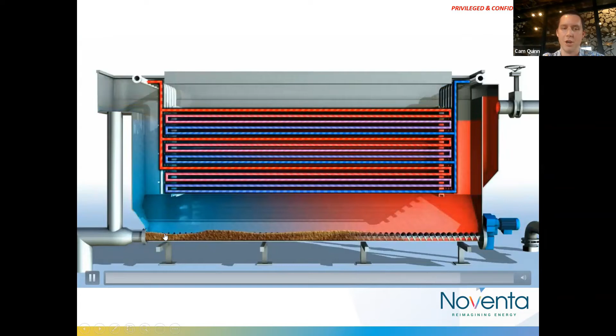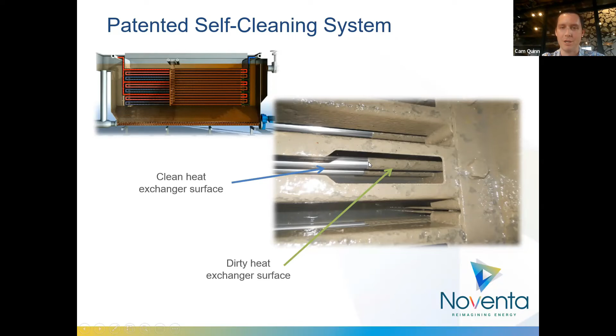Because of this self-cleaning function, we're able to deal with the biofilm growth and solids accumulation. So, in more detail, this is a picture of the inside of a heat exchanger that's been in service. I believe this picture was taken about a year after it went into service. You can see how effective the cleaning is. I want to say fairly perfect heat transfer surface area here, but you can see all the biofilm growth, and most people can imagine you're not going to get great heat transfer where the cleaning didn't go. So this is the technology that we've selected to address the wastewater energy transfer challenges.